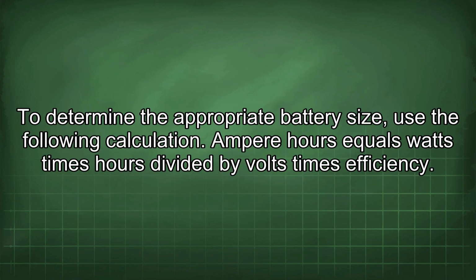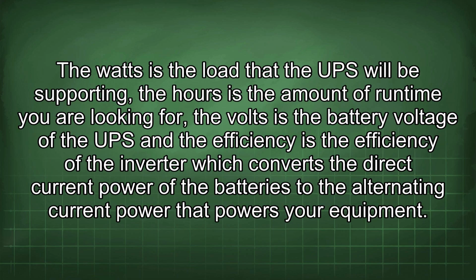To determine the appropriate battery size, use the following calculation. Ampere hours equals watts times hours divided by volts times efficiency. The watts is the load that the UPS will be supporting, the hours is the amount of runtime you are looking for, the volts is the battery voltage of the UPS, and the efficiency is the efficiency of the inverter, which converts the direct current power of the batteries to the alternating current power that powers your equipment.